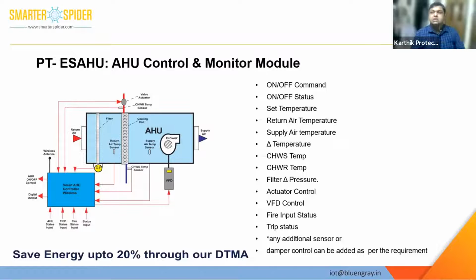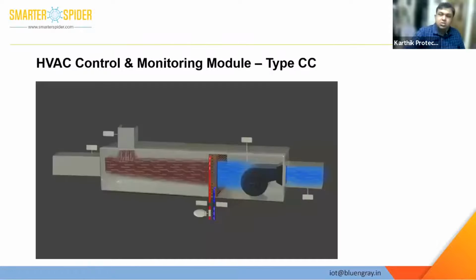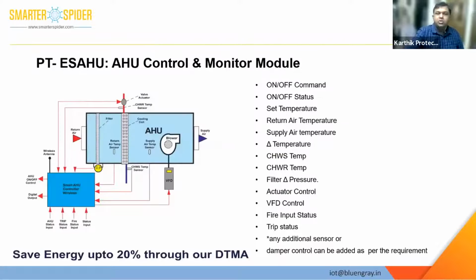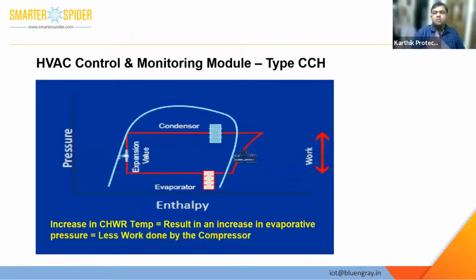Now, coming to the savings part, we provide average savings of up to 20% through our delta T manager. What we are trying to do here is increase the chill water return temperature, which results in an increase in the evaporator pressure, which in turn results in less work done by the compressor. And this is where we tend to save the energy.